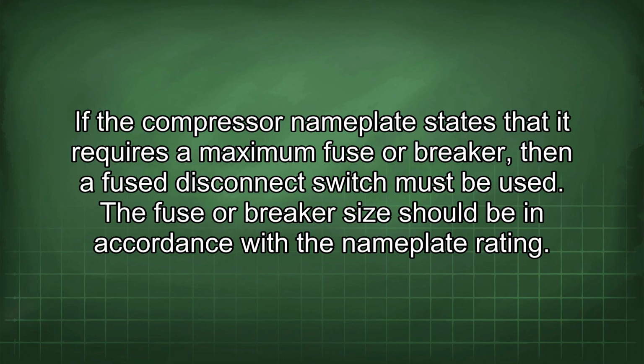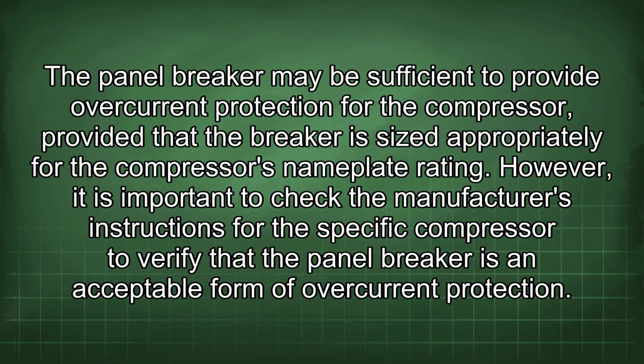If the compressor nameplate states that it requires a maximum fuse or breaker, then a fused disconnect switch must be used. The fuse or breaker size should be in accordance with the nameplate rating. The panel breaker may be sufficient to provide overcurrent protection for the compressor, provided that the breaker is sized appropriately for the compressor's nameplate rating. However, it is important to check the manufacturer's instructions for the specific compressor to verify that the panel breaker is an acceptable form of overcurrent protection.